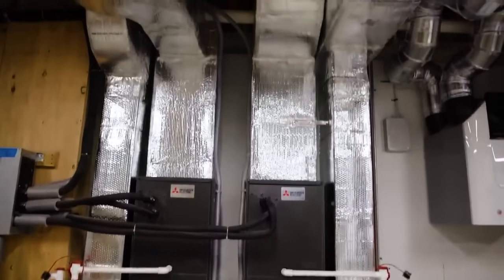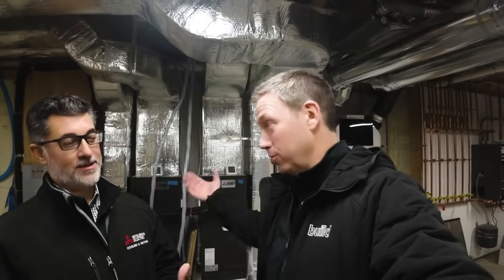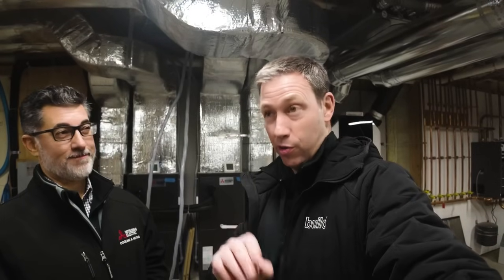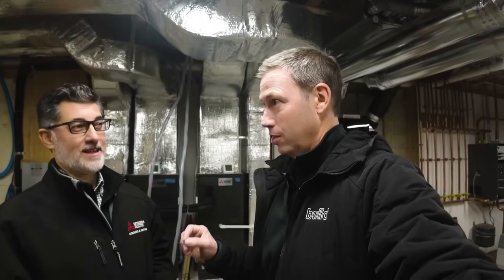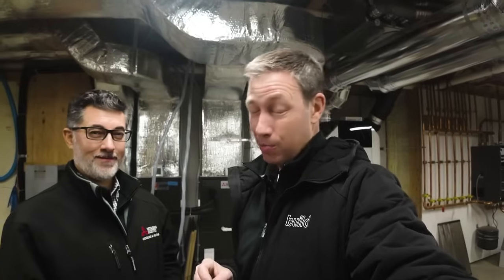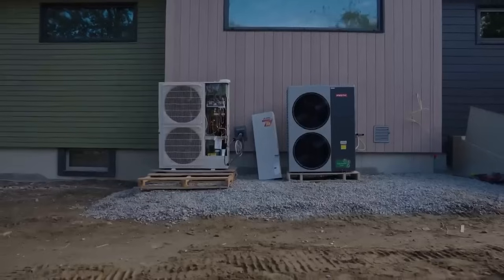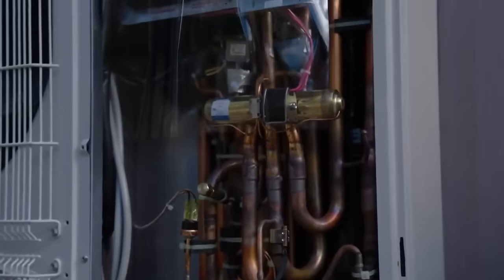Well, they'll produce full capacity heating down to 5 degrees. We have some units that'll go down to -5 full capacity. And this is Fahrenheit, don't forget. Fahrenheit, correct. And down to -13, you'll get about 87% of capacity. Holy cow, -13 out, and we're still pulling 87% capacity. Correct. They'll still operate down to -20 degrees. That's amazing. Now, full disclosure though, they're not as efficient, right? When it's 10 degrees or -10 degrees out there, even less efficient. But you know, in most places of the world, it's not -10 most of the time. Even in snowy Boston, it's December and today's high is in the 40s. So you're gonna be just fine with a heat pump in these conditions.